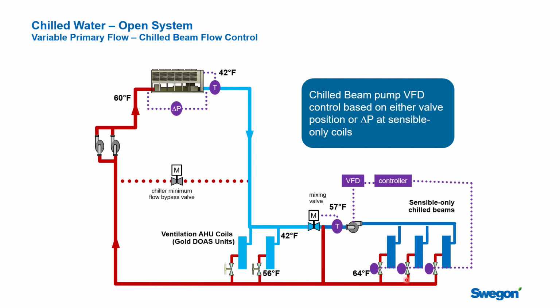If the building automation system is polling all the control zones in the building, all it needs to do is maintain enough pressure to make sure that the zone that has its valve open the most is the one that's being serviced. So rather than just looking at the general pressure of the supply water piping system, we'd actually be looking at valve positions. So you'd typically say that if any valve anywhere in the building gets close to, say, 90% open, you would start to increase the pressure so that the valves don't go fully open and lose control.